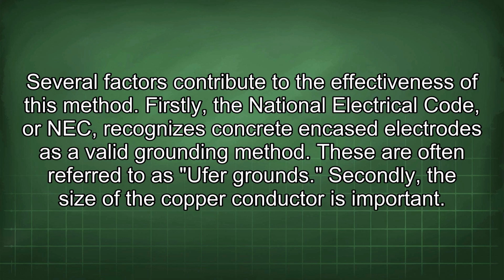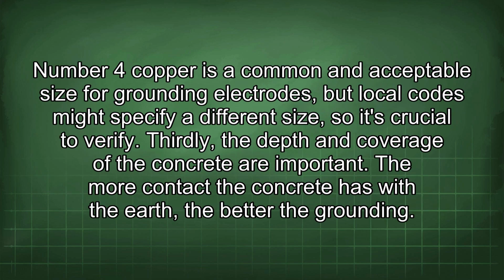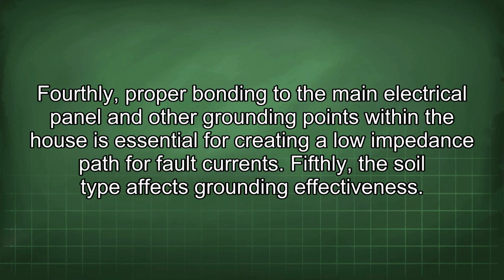Secondly, the size of the copper conductor is important. Number 4 copper is a common and acceptable size for grounding electrodes, but local codes might specify a different size, so it's crucial to verify. Thirdly, the depth and coverage of the concrete are important. The more contact the concrete has with the earth, the better the grounding. Fourthly, proper bonding to the main electrical panel and other grounding points within the house is essential for creating a low impedance path for fault currents.